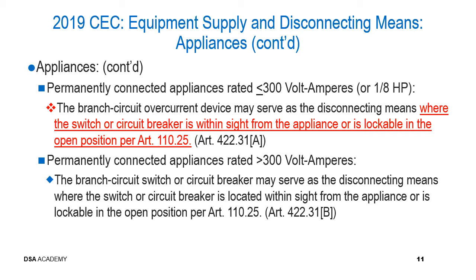to the 2019 version of the California Electrical Code, and that is where the switch or the circuit breaker is within sight of the appliance, or again is lockable in the open position per Article 110.25. And this information comes from Article 422.31(A). The next situation is a permanently connected appliance that's rated over 300 volt amperes.